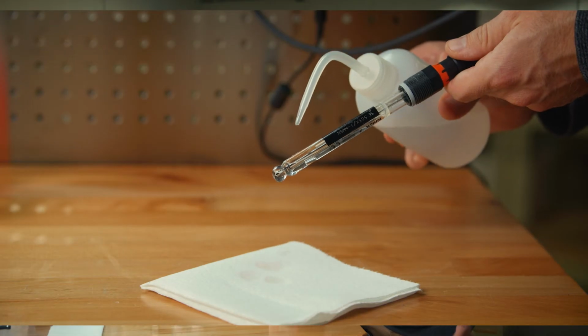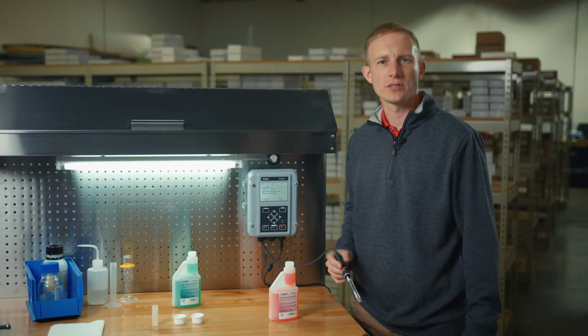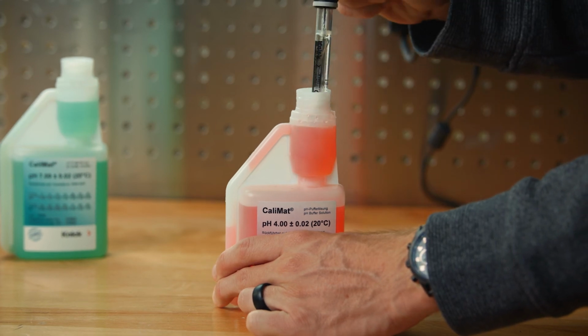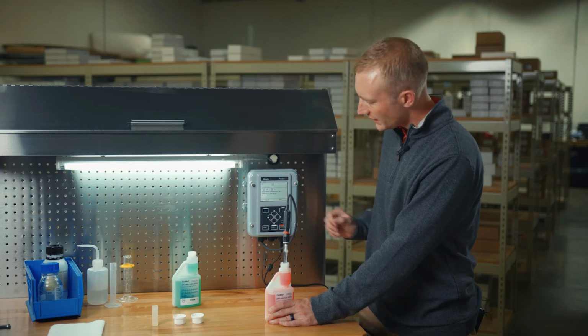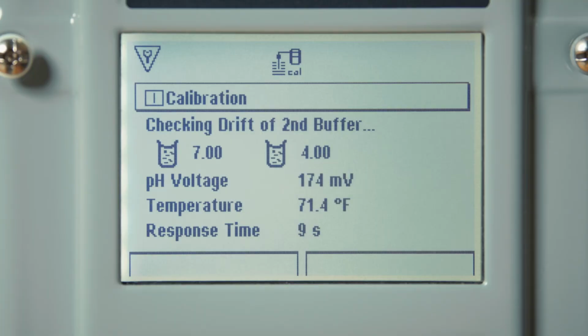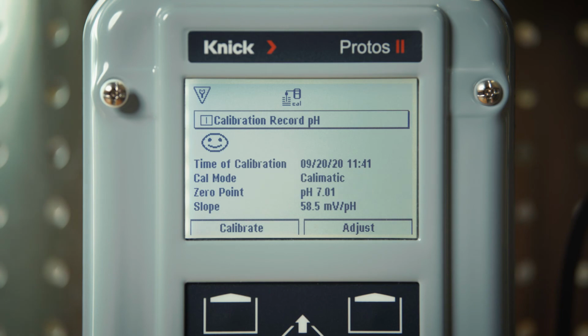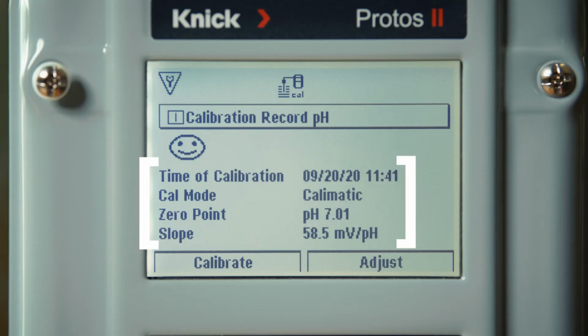We will do so and then place our sensor in the buffer 4 solution. Again, stir lightly and then press Next to proceed to the next step. As with the first step, you can see that the transmitter automatically recognizes the buffer value and displays the pH voltage, temperature, and response time. Once complete in the second buffer, our Protos displays the specifics of your calibration record.